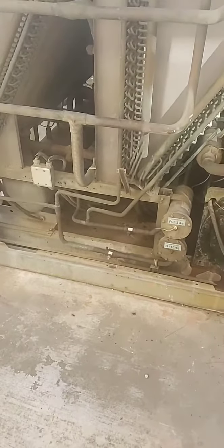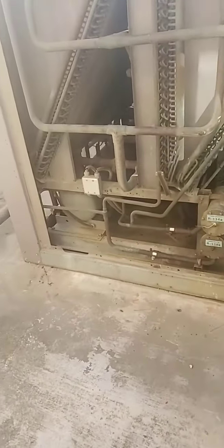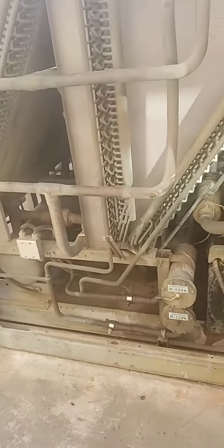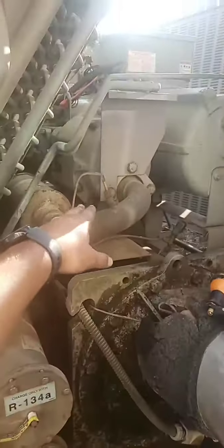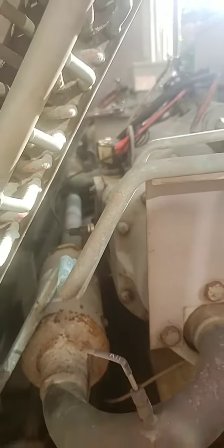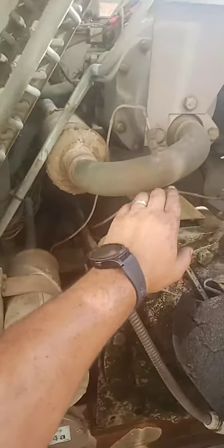But these screws, when you ever work on them, you're going to learn that they're notorious for being very loud, and you always want to wear ear protection when working around them. Alright, so you can see the backside of compressor B here. You can see that right there, that's your high pressure switch. And then you can see the backside of the unloaders and the slide. My camera is trying to focus here. And so these ports here, these are coming off of your oil separator. Like I said, this is your discharge line. This is a discharge muffler.